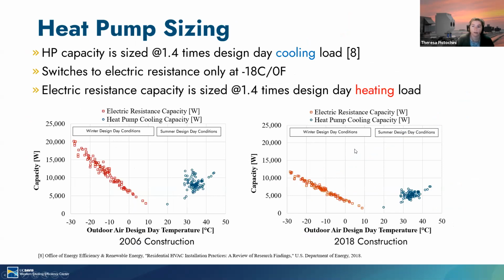The simulation auto-sizes the heat pump capacity in every climate simulated at 1.4 times the design day cooling load, which is a typical method for sizing heat pumps. We experimented with different heat pump sizing methods, but found that increasing the heat pump size to meet large heating loads generally provided minimal benefit. This is because on the coldest days in the coldest climates, the outdoor air conditions are below that negative 18 degrees C switchover temperature, such that the electric resistance heat has to meet the load alone.